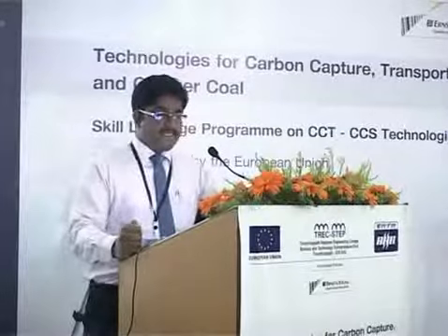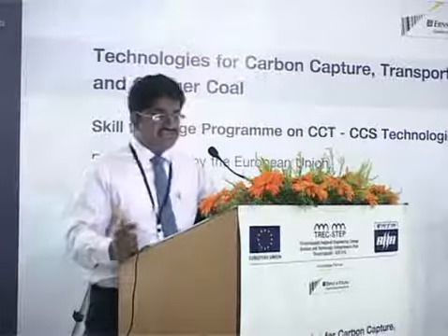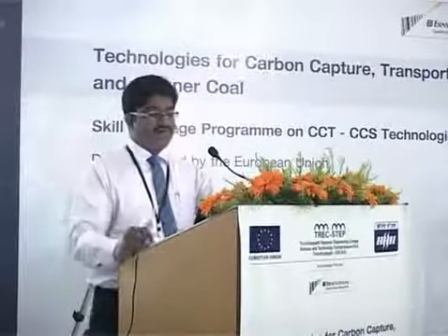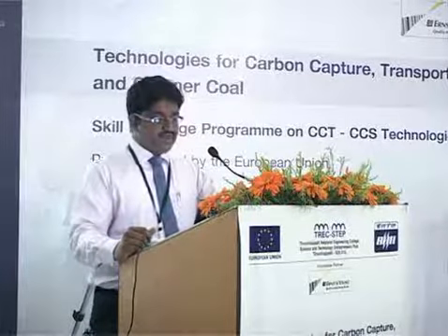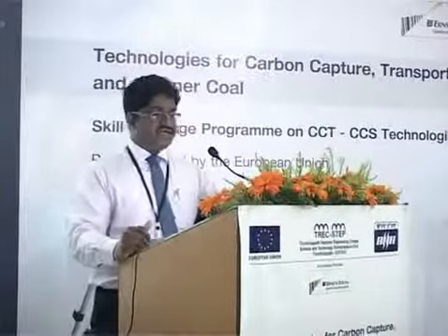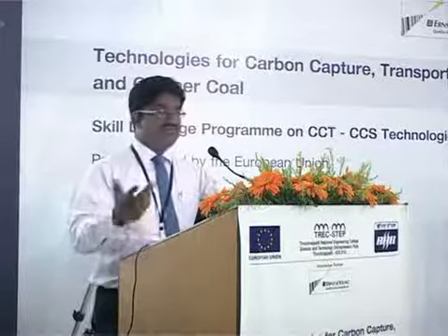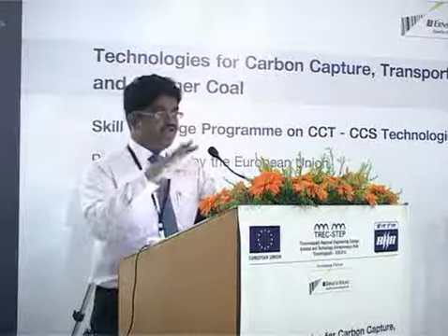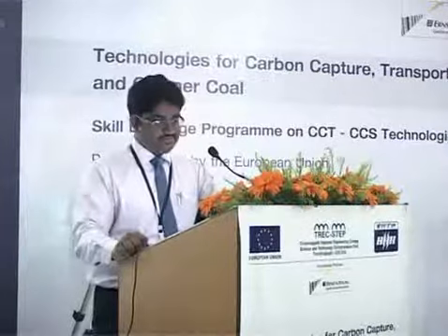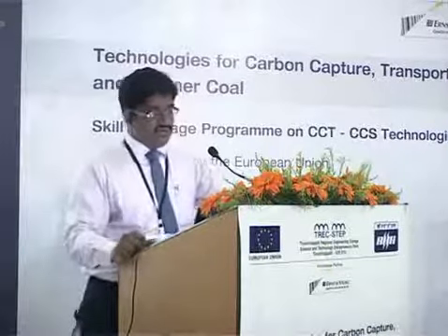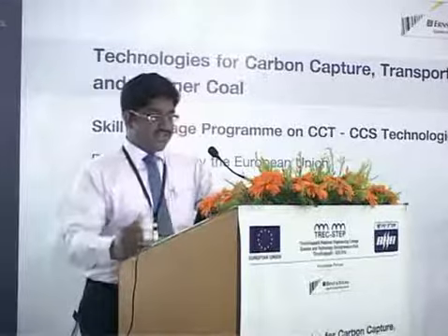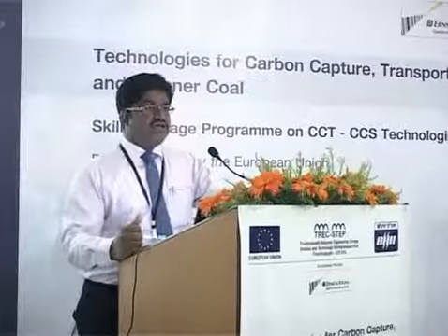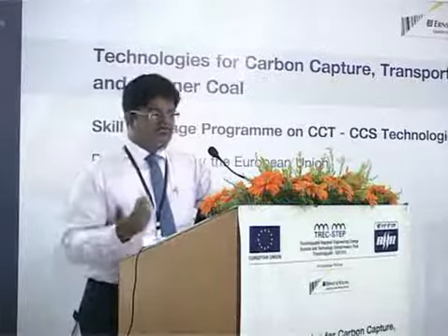If you see an electrical energy saving project, roughly 1 unit will get you about 0.9 to 1 kg of CO2. And from renewables, it's about 1 megawatt will give you about 4,500, depending upon the plant load factor. And 1 kg of coal will get you about 1.8 to 1.6. There is a fuel oil saving figure that we have. So now, how to take it up?